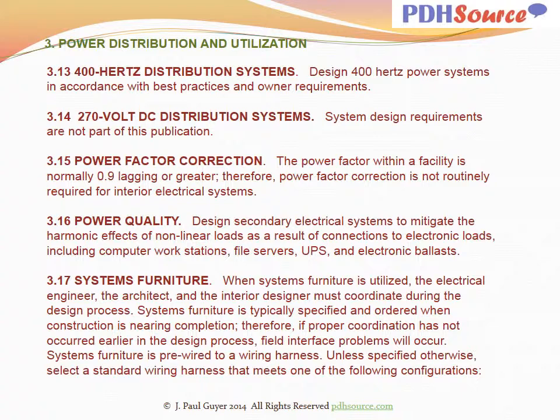Power factor correction. The power factor within a facility is normally 0.9 lagging or greater. Therefore, power factor correction is not routinely required for interior electrical systems. With regard to power quality, design secondary electrical systems to mitigate the harmonic effects of nonlinear loads as a result of connections to electronic loads, including computer workstations, file servers, UPS, and electronic ballasts.